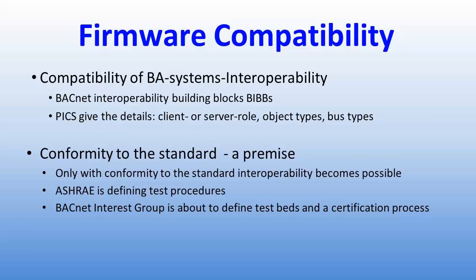Interoperability is the ability of diverse systems and organizations to work together. BACnet accomplishes interoperability through the use of BIBBs, which are BACnet Interoperability Building Blocks. The intent of BIBBs is to provide a way for a specifier to write a performance specification without the need to understand all of the technical details on how it should be implemented. In essence, a BIBB is a simple definition of an interoperability function.